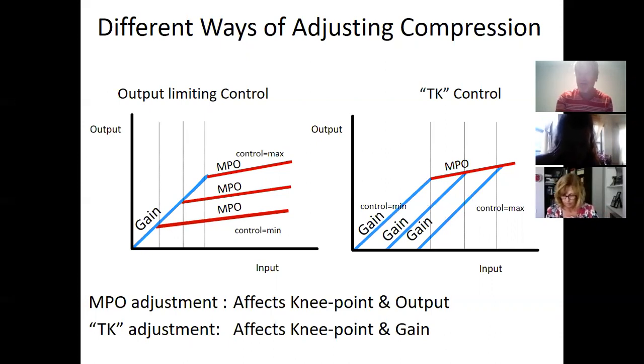The right-hand graph shows you how WDRC is adjusted. And what you're doing with WDRC is you're adjusting the gain for soft inputs. You're talking about the floor. You're not worried about the ceiling. Mrs. McGillicuddy with a 40 to 50 dB sensorineural loss isn't wearing a high power hearing aid. She's wearing a weaker hearing aid. So your concern isn't limiting the maximum power because otherwise you'll make her more hard of hearing. Of course you don't want the MPO to be really loud, but the focus is on how much gain I want to give for soft sounds.